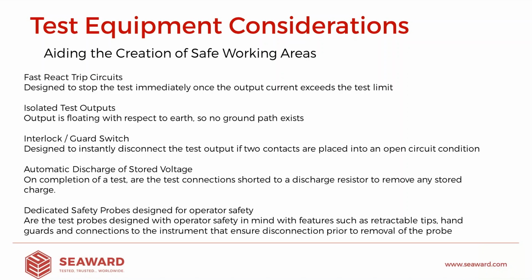We can also look for isolated test outputs. So the isolated test outputs are floating with respect to Earth, so effectively removing that ground path, which means that if the operator was to come into contact with one of the test outputs, there is no path to ground through the instrument, so therefore they're kept nice and safe.